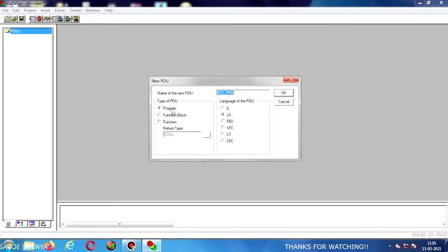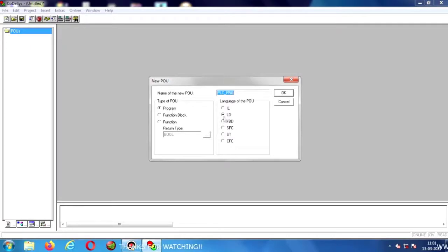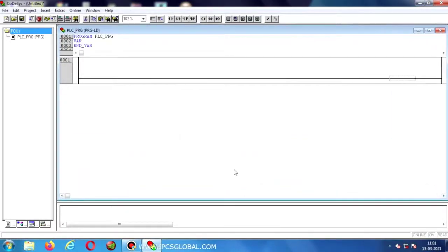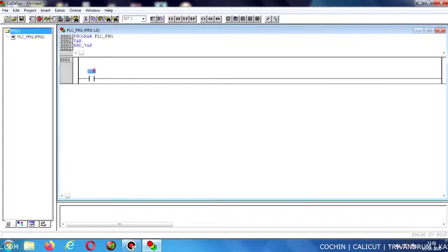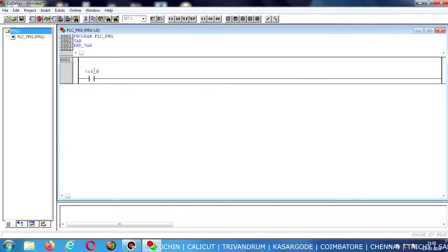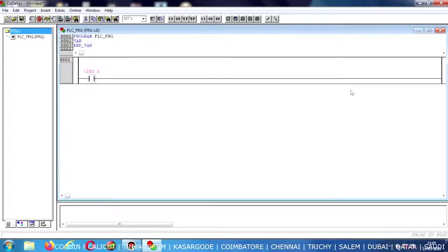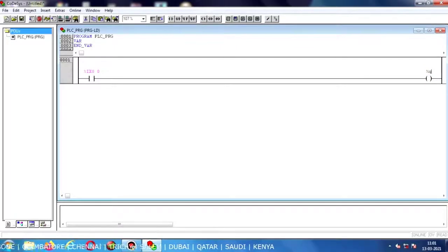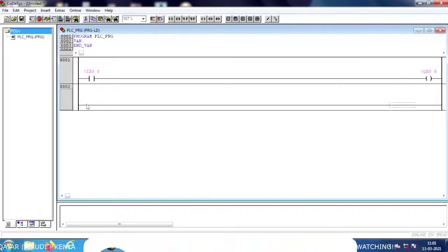Now I am selecting the type as Program and the programming language as Ladder Diagram, so I am choosing Program and LD. Click OK and the new file will be created. In that I am using a NO contact and giving input address %I0.0, connecting it with output coil %Q0.0.